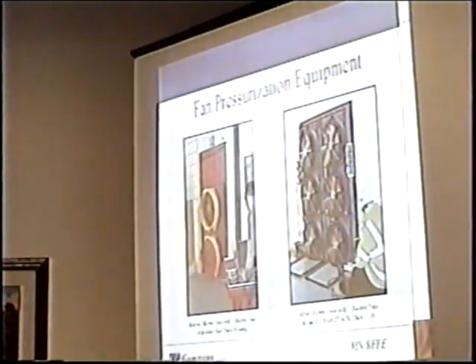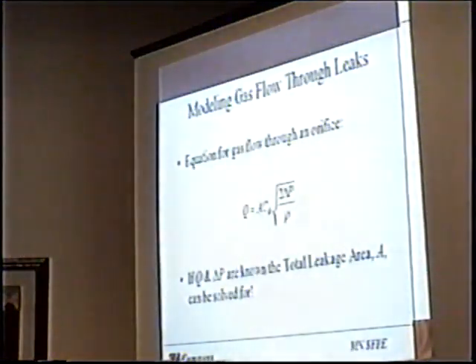So here are just 2 example setups. We can take these racks of fans and install them into a door or a window and essentially pressurize or depressurize the enclosure by running them forward or reverse. And we can simultaneously measure the airflow rate through the fan, as well as the pressure disparity between the inside and the outside of the enclosure. So using that, we can take our orifice flow equation. Now this is fairly rudimentary. You can pull it right out of Bernoulli's streamline equation. Essentially rooted there originally.